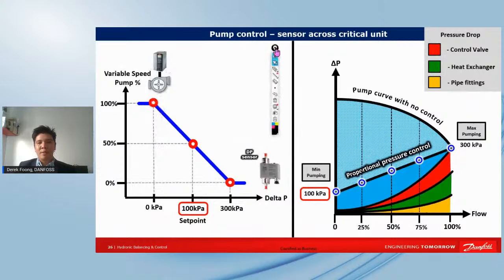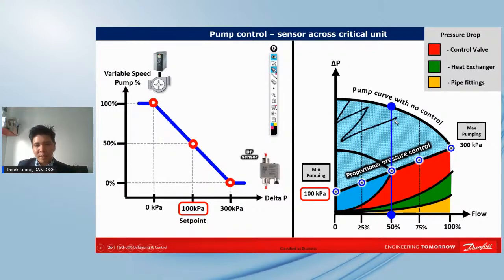So, this is exactly what I've mentioned about proportional pressure control. It allows you to have a lower minimum pumping set point, say 100 kPa, which is placed at the critical unit. Whenever the flow reduces, the pump will be able to reduce the pressure at the same time. So this blue shaded area is the energy saving part. For instance, if we have 50% of the flow rate, then the pump curve would be even smaller. So the potential energy saving area is at this area.